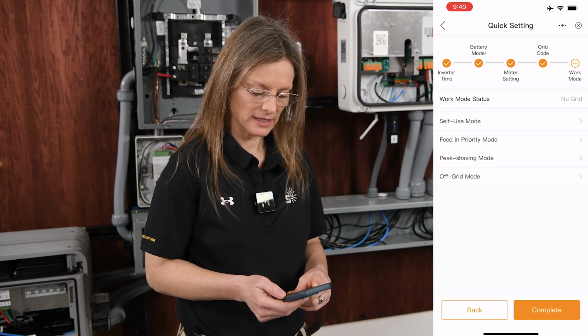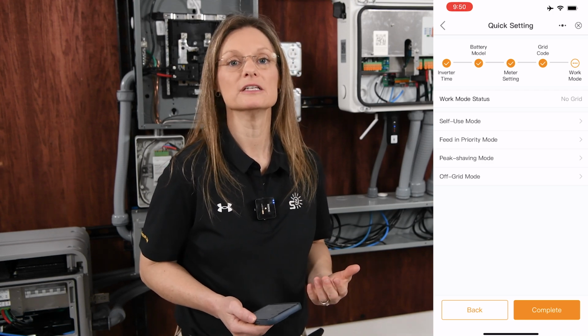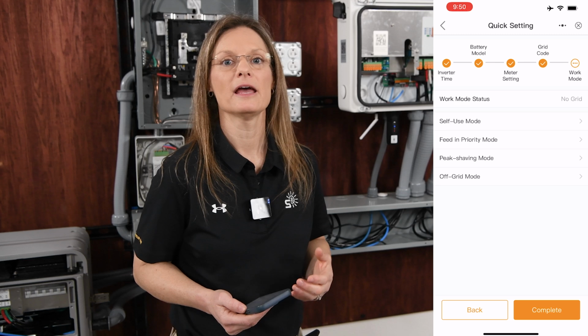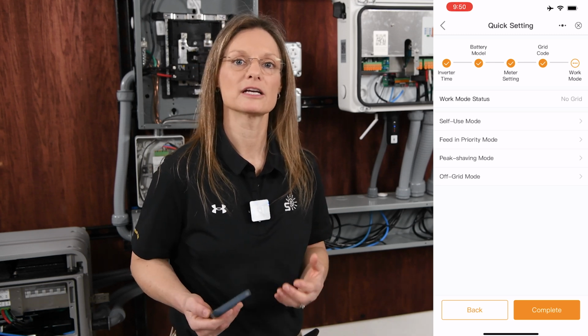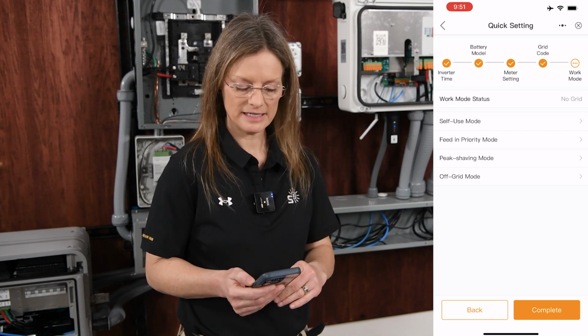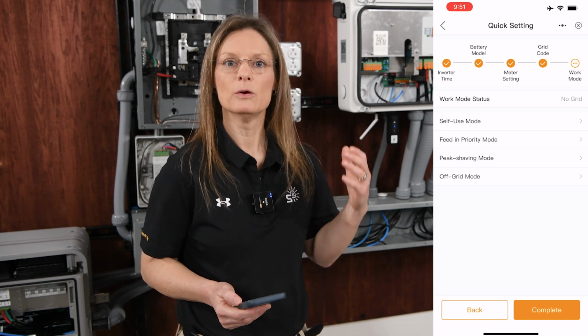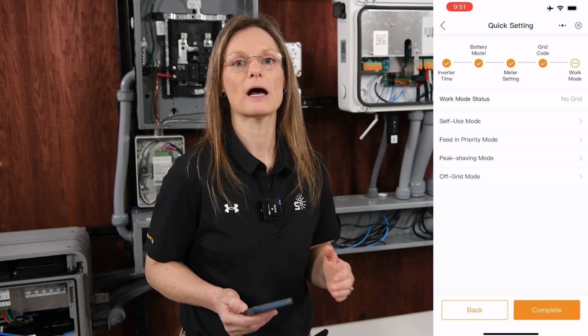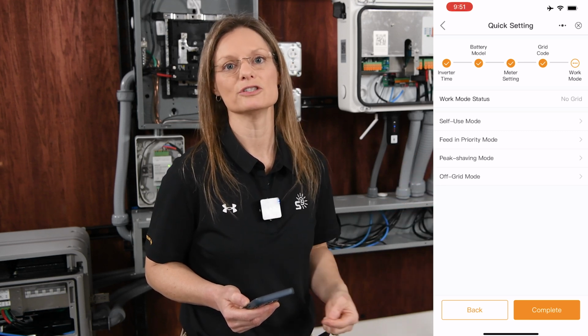Our last option is to select our work mode, and the first option on this is self-use mode. Now you would want to select self-use mode to determine what your priority is from your PV. If you want your PV to first go to your loads and then to your batteries, and then once your batteries are fully charged to export back to the grid, that's the one that you would want to choose. The next option that you have is the feed-in priority mode. This would prioritize the power that you're bringing in from PV to feed it first to your loads and then export power back to the grid as your second priority. You would set up the cap that you want to export back, and if there's any excess after that, then you would tell it to charge your batteries.